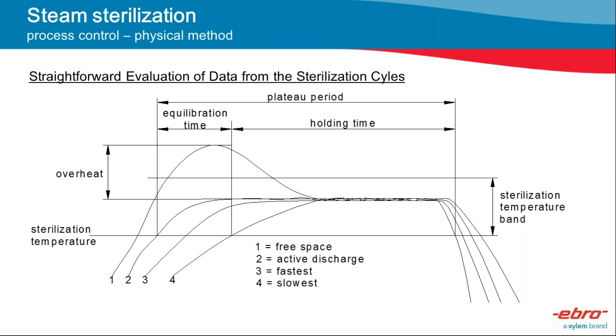It can automatically detect the different stages of your sterilization cycles, from the heating to the come up to the equilibration time up to the holding time, and even when you require it, it can also give you some information about how it's being cooled during the process. And it will automatically give you an indication whether it's a passing sterilization process or a failing sterilization process.